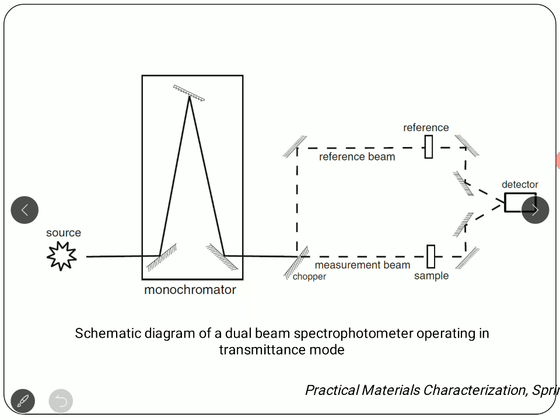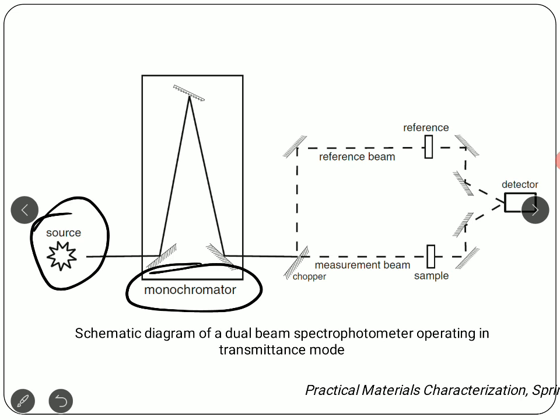Continuing, we will now discuss the instrumentation part. A spectrophotometer generally has a source, followed by a monochromator which separates out wavelengths. If we want UV radiation of a particular wavelength incident on a sample, we use a monochromator, which may be a combination of a grating and mirror. The mirror reflects the beam, the grating separates the wavelengths, and the light travels further.